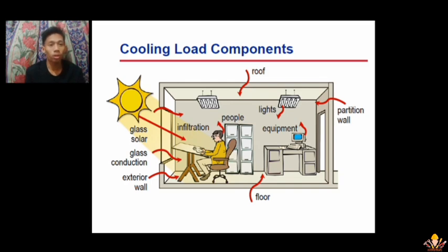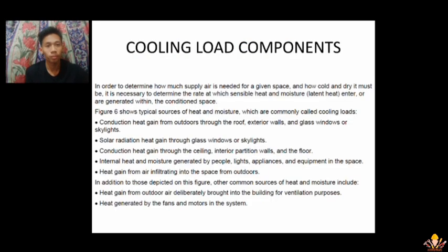We have the cooling load components. In order to determine how much supply air is needed for a given space and how cold and dry it must be, it is necessary to determine the rate at which sensible heat and moisture, or latent heat, enter or are generated within the conditioned space. Figure 6 shows typical sources of heat and moisture, which are commonly called cooling loads.